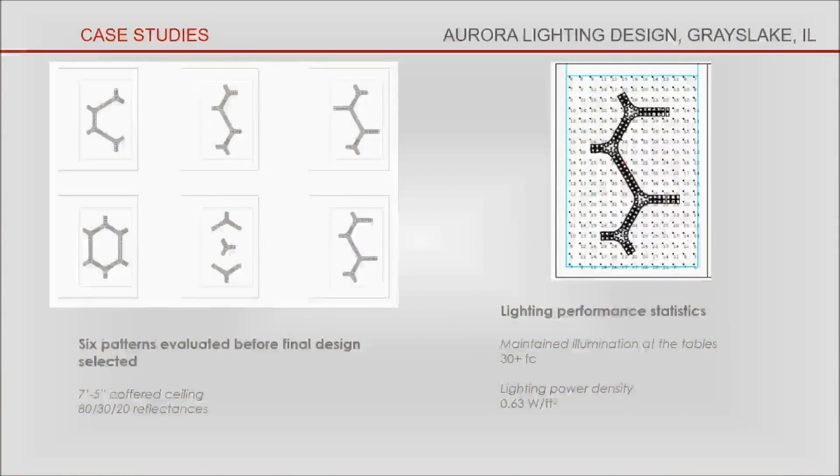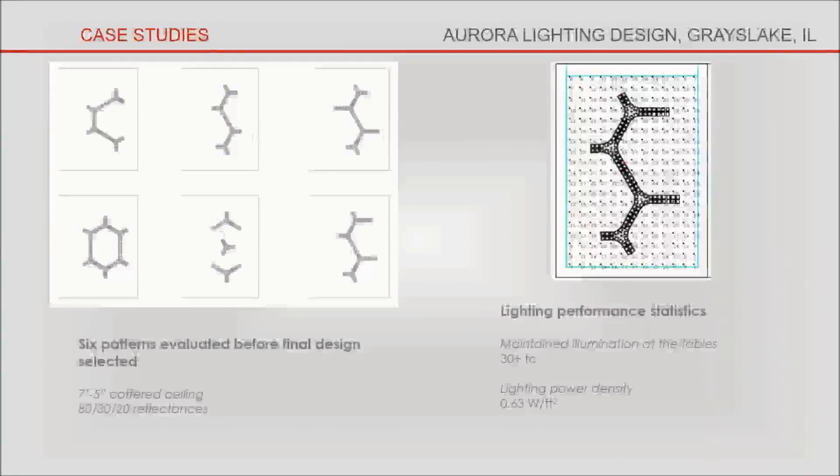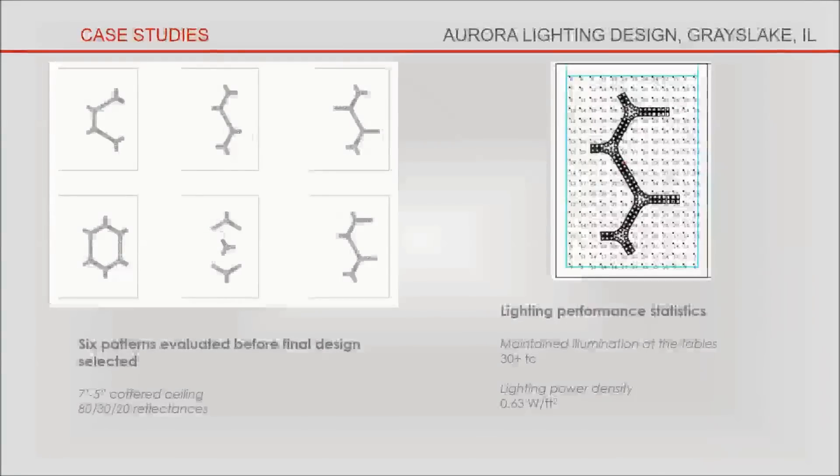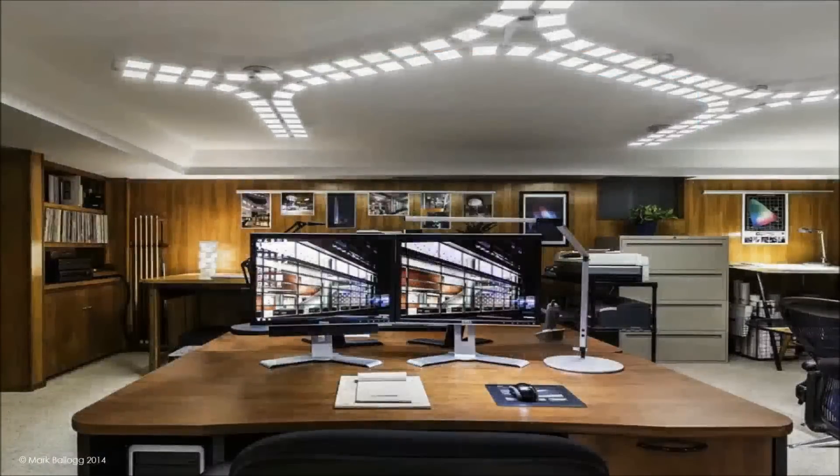Six patterns were evaluated before the final design was selected, resulting in maintained illuminance of 30-plus foot candles at the work surfaces and a lighting power density of 0.63 watts per square foot. The end result is functional and inspiring.